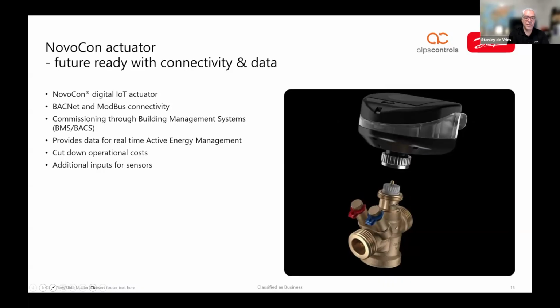This also gives you a rather interesting feature. As I was explaining, the way the valves have to be set then disappears, because you can do the setting from behind the computer using the digital actuator, which also makes it a lot easier to make corrections. In the building planning process, often we wanted to have 5 offices here, but now we want 3 and a big meeting room. Can you please make it happen? Then maybe you need a bit different flow, or to arrange the valves in a different way. This will be much easier when you have digital access to your actuator.